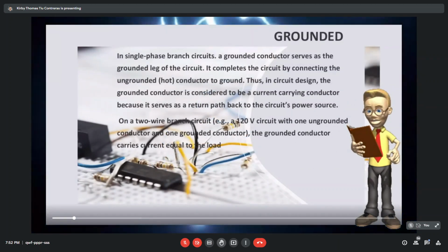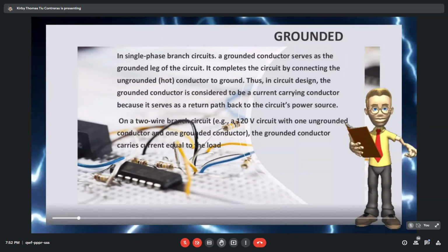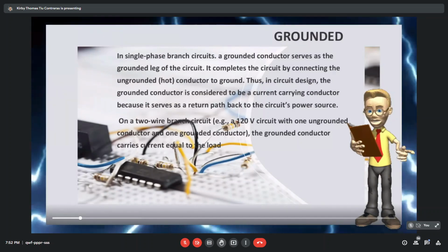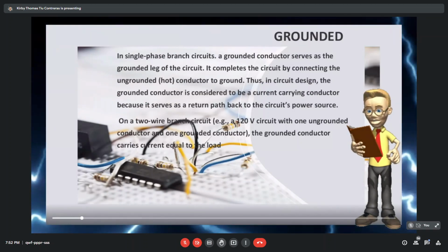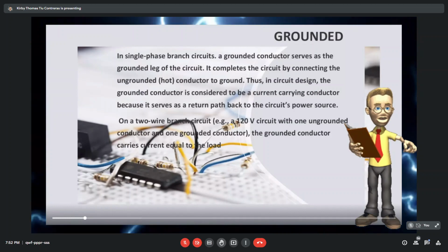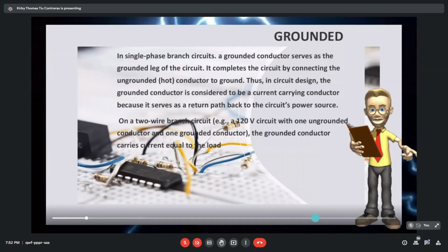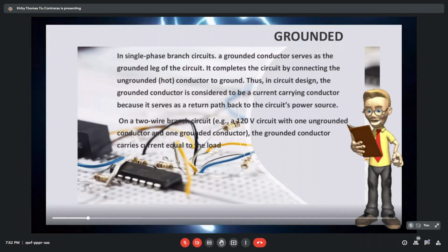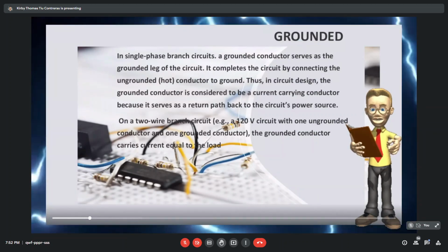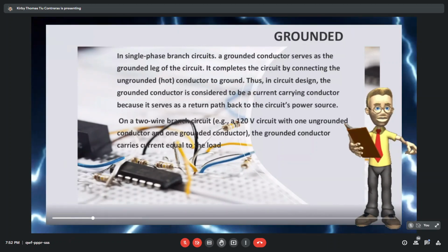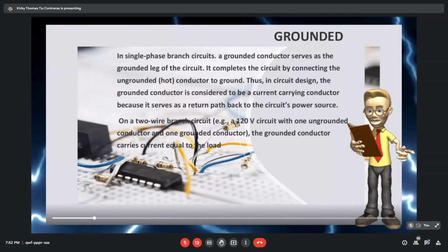Grounded conductor. In a single-phase branch circuit, a grounded conductor serves as the grounded leg of the circuit. It completes the circuit by connecting the ungrounded, which is the hot conductor, to the ground. Though in the circuit design, the grounded conductor is considered to be a current-carrying conductor because it serves as a return path back to the circuit power source. So, on a two-wire branch circuit, a 120 volt circuit with one ungrounded conductor and one grounded conductor.